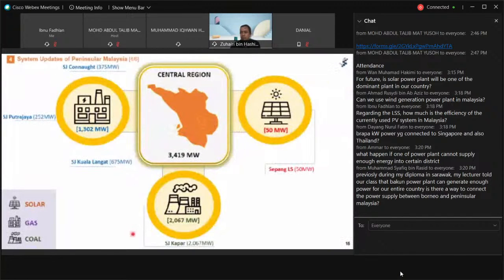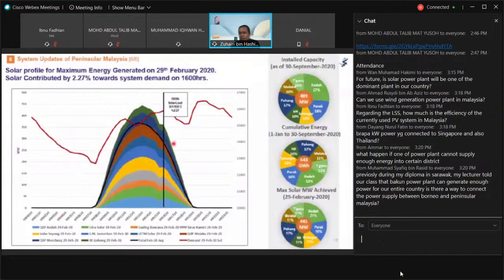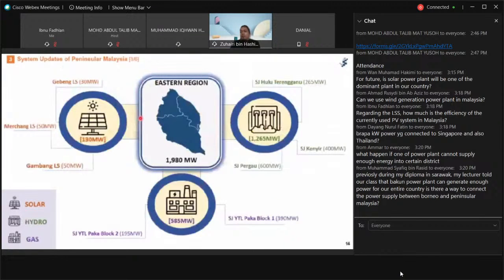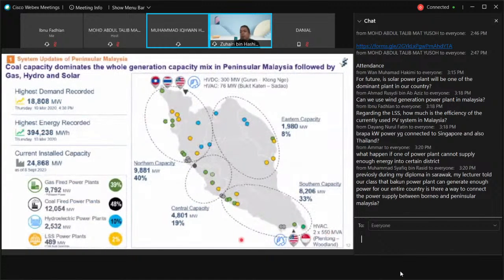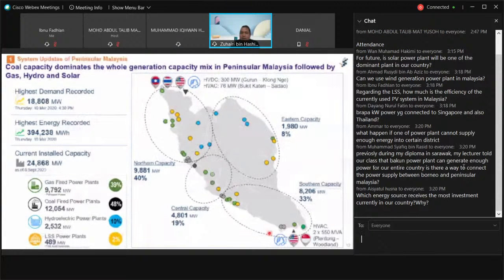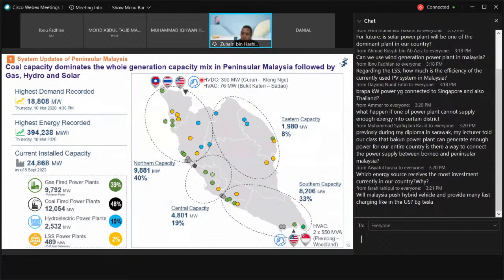How many kilowatts of power are connected to Singapore and also Thailand? As mentioned by my colleague Izzuddin, with Singapore we have 2 submarine cable connections via HVAC, 2 by 550 MVA. With Thailand we have 376 megawatts - 300 megawatts via HVDC link, and another link with IGAT via HVAC at 76 megawatts. Normally the HVDC link with Thailand is heavily used every day to import and export energy between both countries.